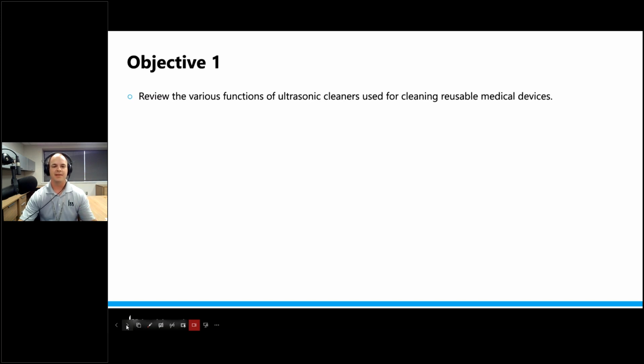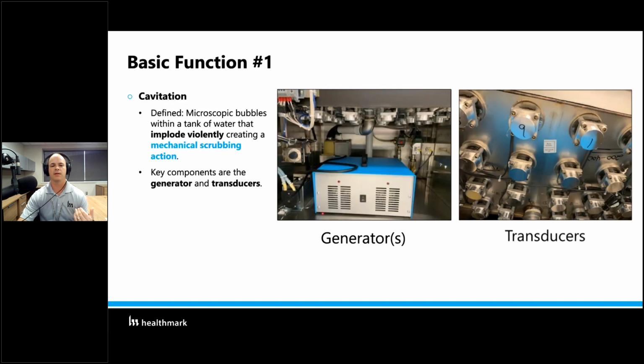Obviously, that's one of the big ones with ultrasonic cleaners and sterile processing. Now, the reason I separate these two out, because you might be asking yourself, well, doesn't it take cavitation in order to remove surgical soils? Well, in a sense, yes, it does, but you could still remove some surgical soils without the presence of cavitation, just by virtue of soaking the instrument. So it's really important to understand that, in my opinion, that there are two different distinct functions there, and that we want them both to be working.